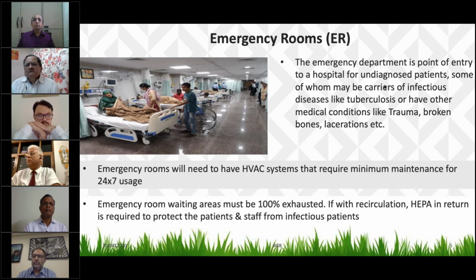And the recommendation for emergency rooms and waiting areas is that they must be 100% exhausted. If anyone is contemplating recirculation, it has to be with HEPA in the return air, to protect the patients and staff from infectious patients. Next slide.